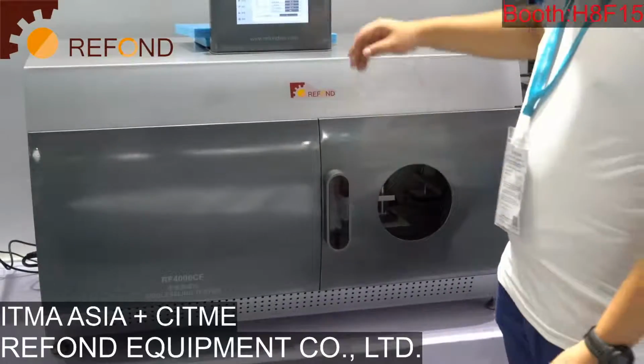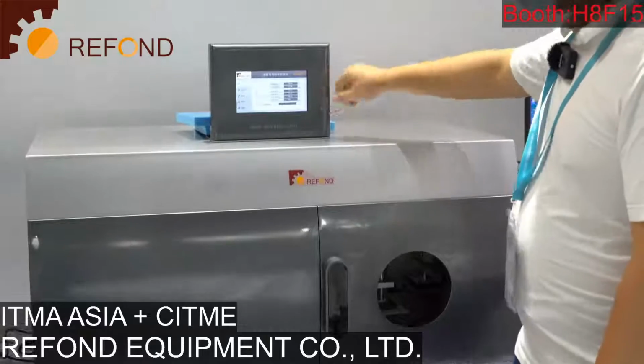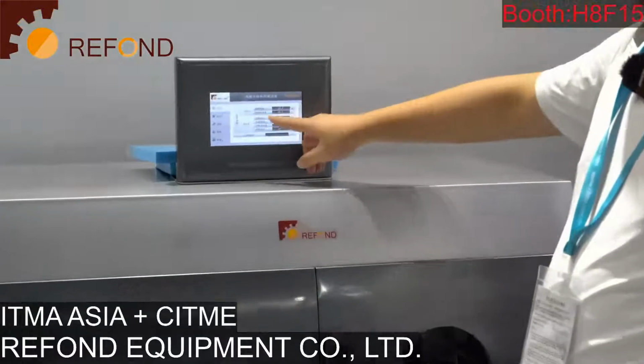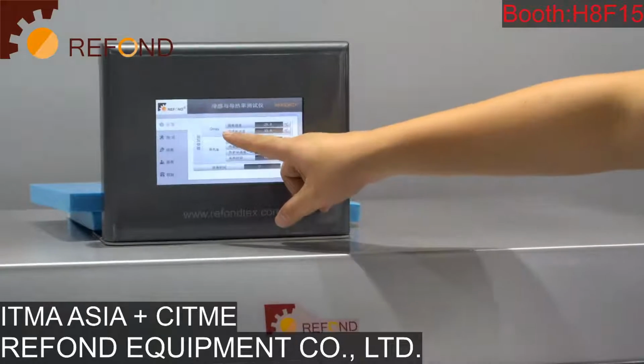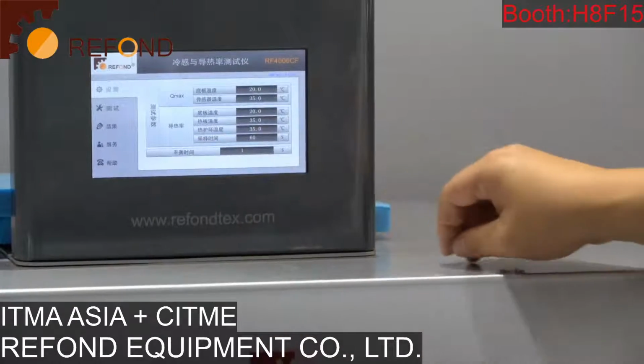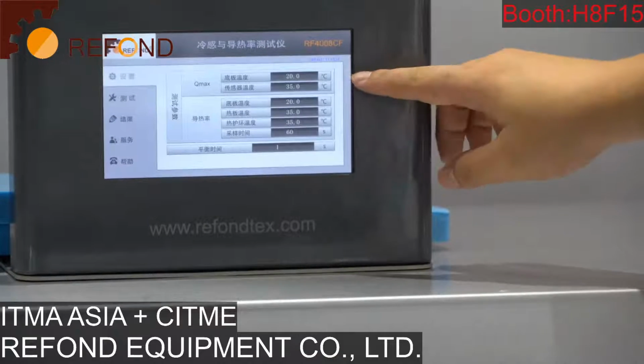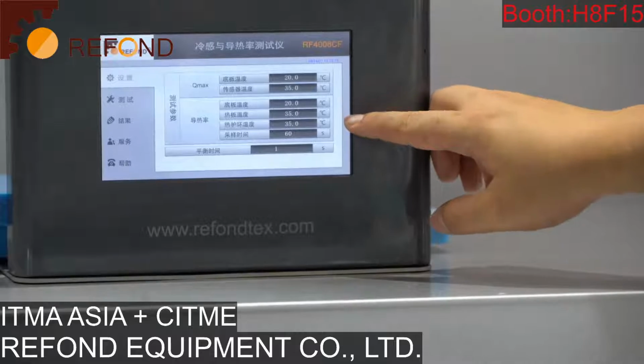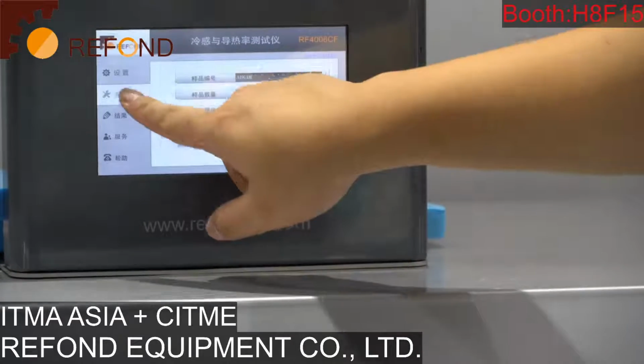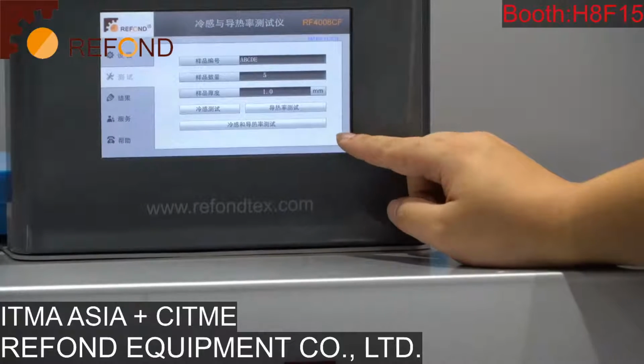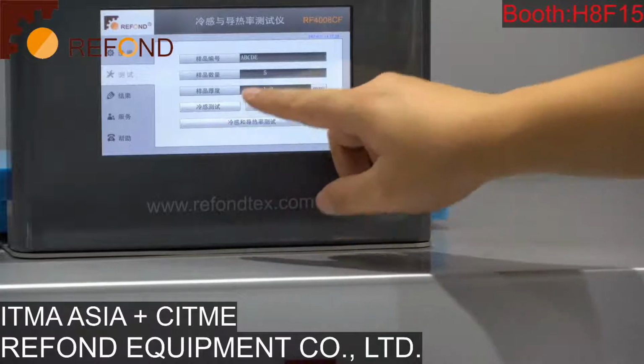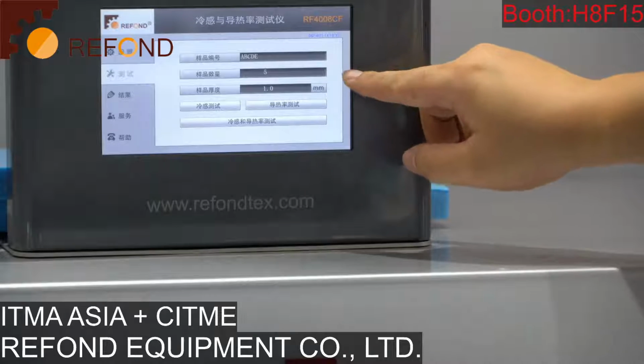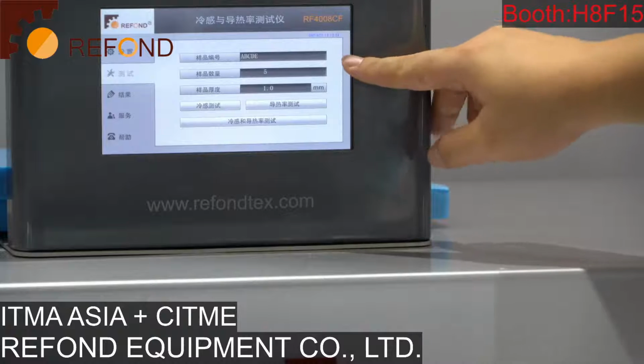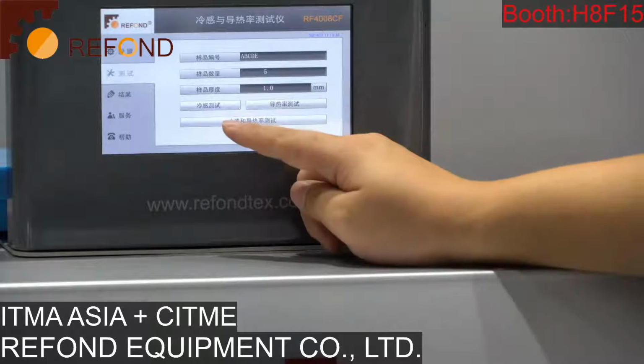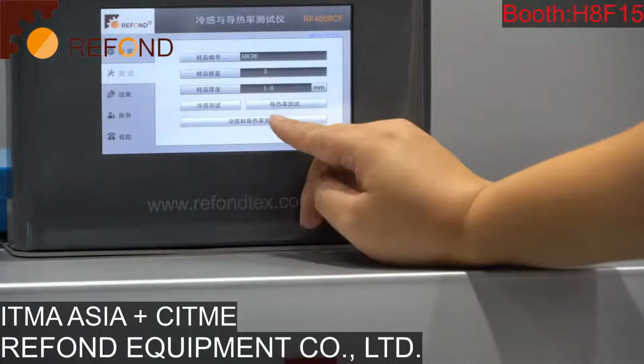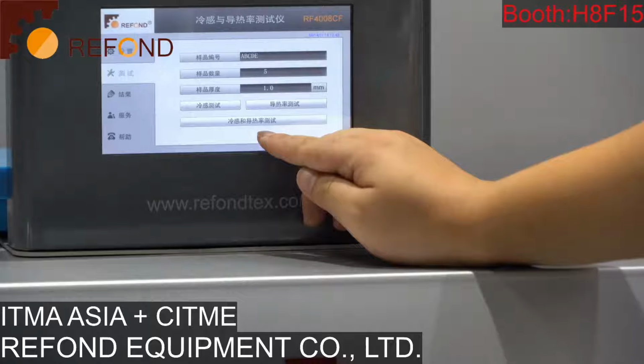The machine has a touch screen. On the touch screen, you can set the test parameters for the Qmax, which is the cool feeling test, and also the heat conductivity test. You can set the temperature of the test head, the temperature of the base plate, and also other test parameters. In the test tab on the touch screen, you can choose how many samples you want to test and the sample code. Also, you can choose whether to do just the cool feeling test, just the heat conductivity test, or do both tests at the same time.